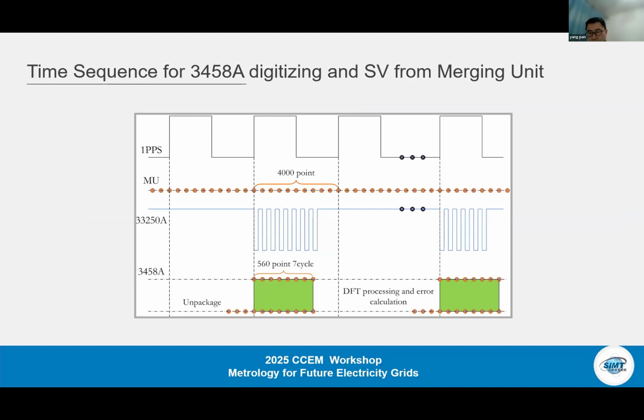So the synchronization sequence between the MU, function generator, and the DMM, including settings for them, is uniquely designed. For an electronic transformer with a sampling rate of 4K, the MU multicasts the sampling values marked with numbers from 0 to 3,999, which is registered in the application data unit, APDU, of the Ethernet frame according to the protocol of IEC 61850-9-2. Having received the electrical PPS from the MU, the pulse generator generates a burst of pulses with a preset number, which further triggers the DMM for digital sampling within the same second as the merging unit.